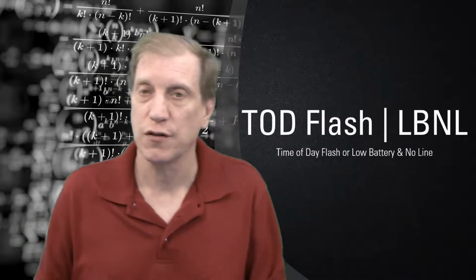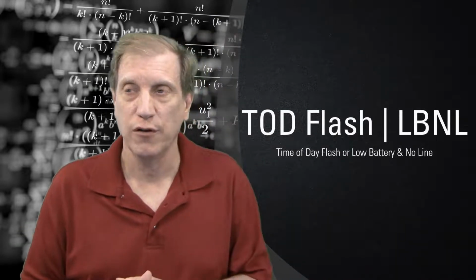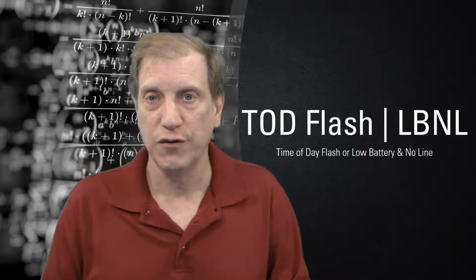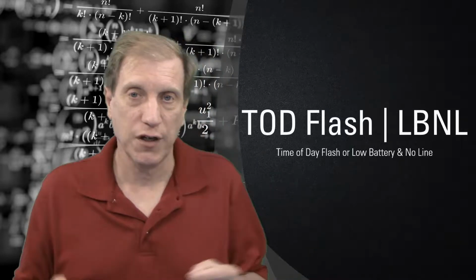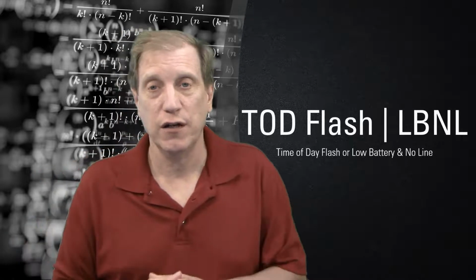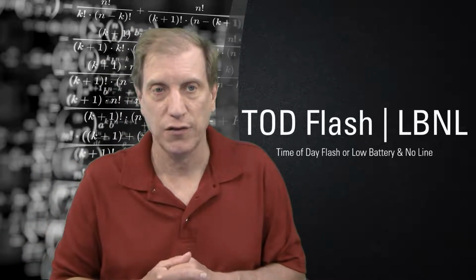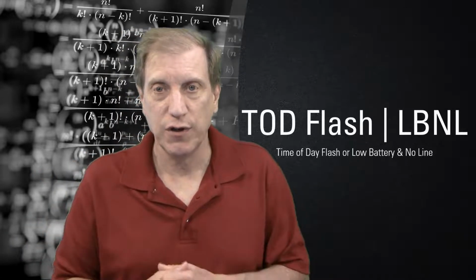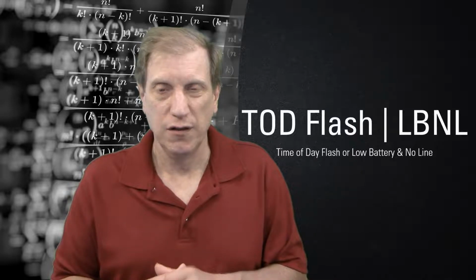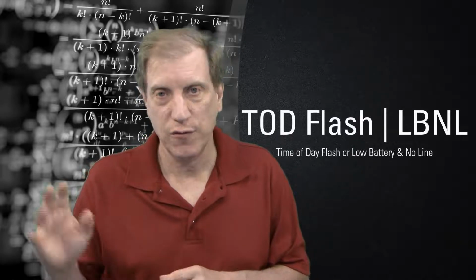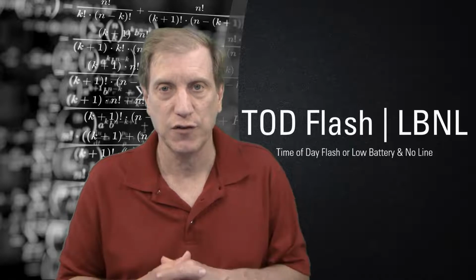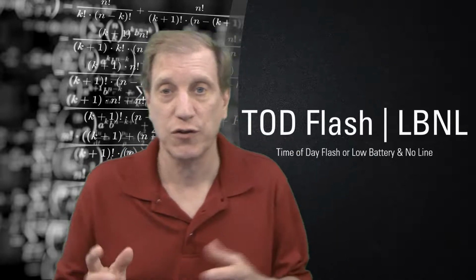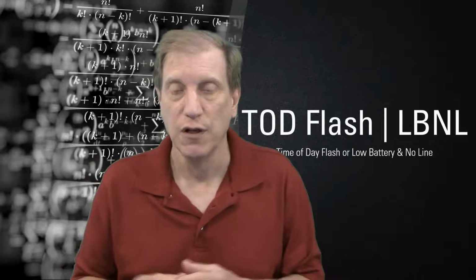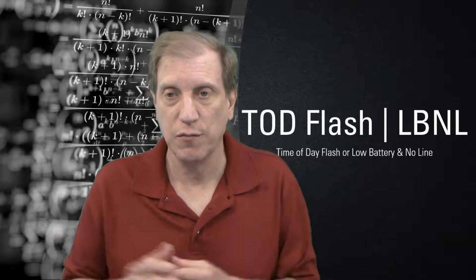Okay, so this next one is time of day flash or low battery, no line. So let's say, for example, you want your intersection to go flash in the middle of the night if you have an outage, just immediately to flash, no full ops. I've had quite a few customers request this over the years. You know, after 10 o'clock and before 6, just go to flash first. Maybe you've got extended outages and you want to make sure that you've got runtime out there for whatever reason. Obviously to keep signals running.